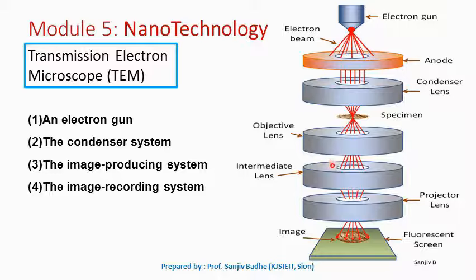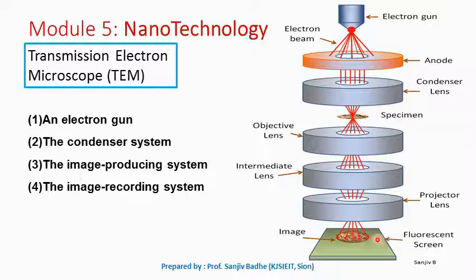If more magnification is needed, it may be obtained by photographic or digital enlargement. The image is obtained on the fluorescent screen. The final part is the image recording system, which converts the electron image into a format that can be seen by the human eye. It consists of a fluorescent screen for viewing and focusing the image, and a digital camera for recording the image. Computerized images are stored in a format such as TIFF or JPEG and can be analyzed and processed to get the final image.